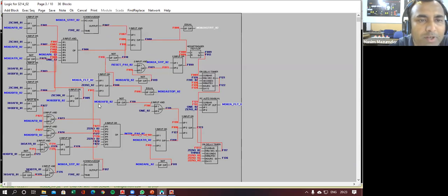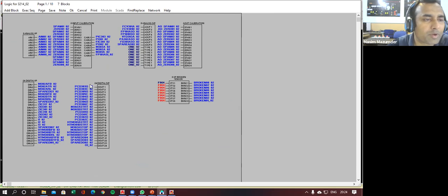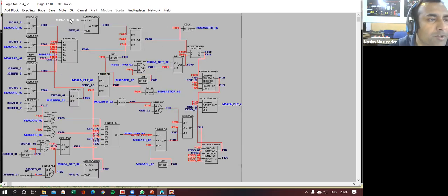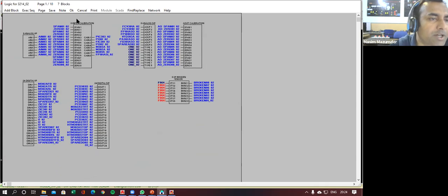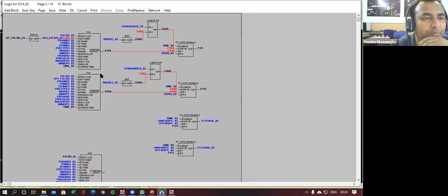Now you go once again to the same, and my connection is unstable. So suppose I am trying to find this particular tag, M302A start underscore 02, and I go to my main page. See here, this particular tag has not been assigned to any pin. I have highlighted this one, M302A start underscore 02. It has not been assigned anywhere in my cards. These are the card pins that I can see, these are the channels, and they are not assigned with this particular tag.